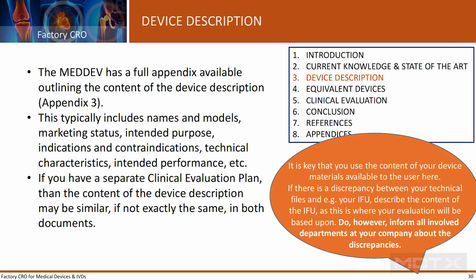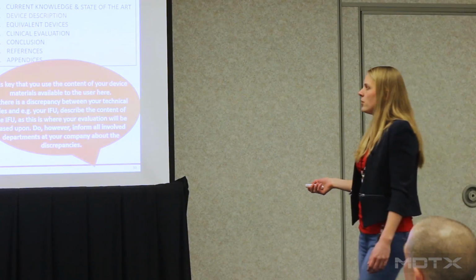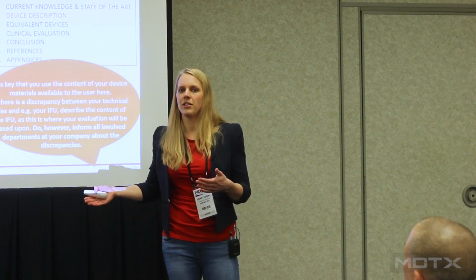If you have a clinical evaluation plan as a separate document, you have the device description in there as well. I would advise to copy-paste it or to refer again to this clinical evaluation plan. Use the content of your device material that you provide to the user, so in your instructions for use or your surgical technique or on your website. But if you identify a discrepancy between your technical files, for example, and your IFU, do make sure that the rest of your team is aware of that as well, because otherwise it will stay like that.